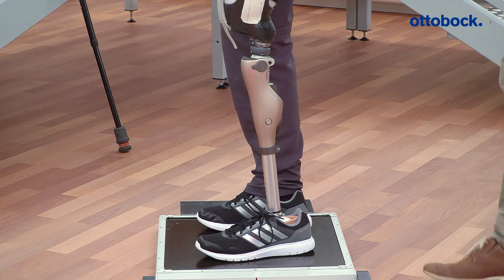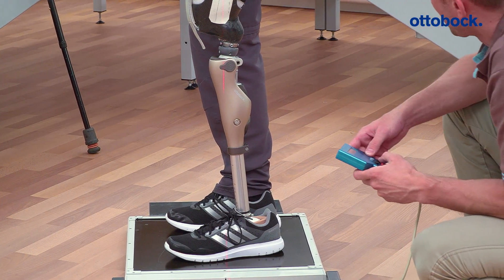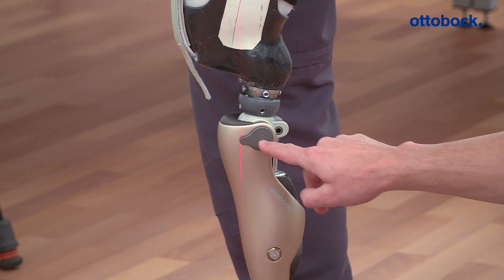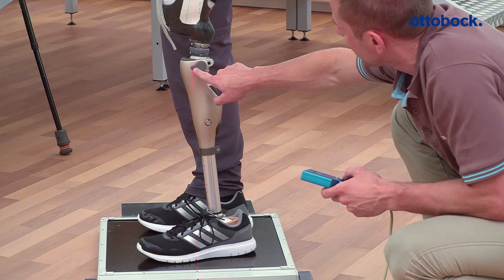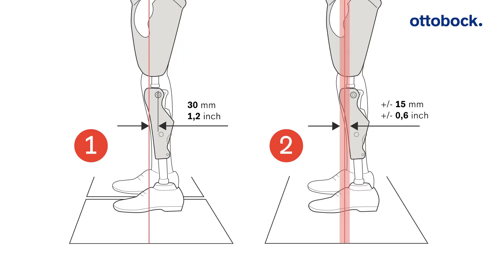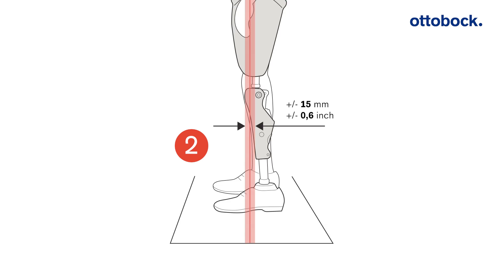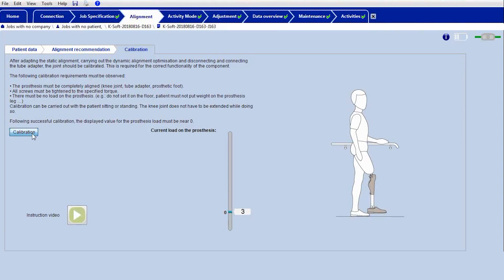The user should now stand with both legs on the L.A.S.A.R. Posture. The weight line is determined in this position. The distance between the weight line and the vertical load line gives you good insight into any horizontal forces affecting the user and how he or she is working to compensate for these forces. The difference between the two measurement situations should not exceed 15 mm. Take into account that recalibration should be carried out after every change to the prosthetic alignment.